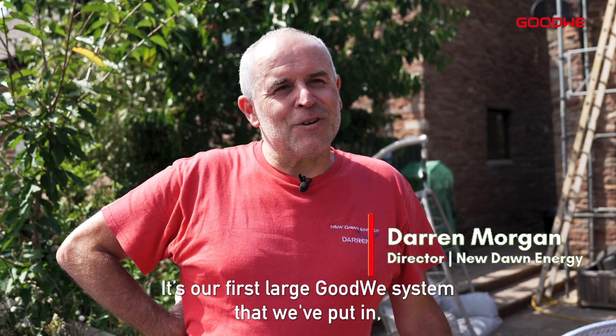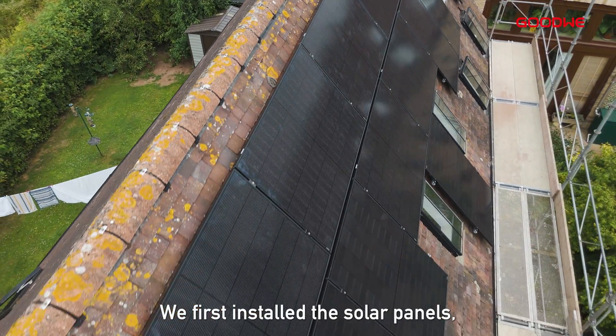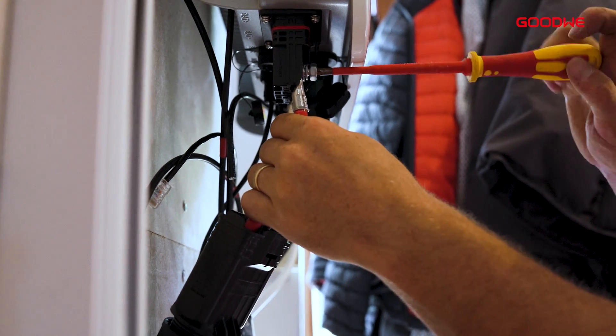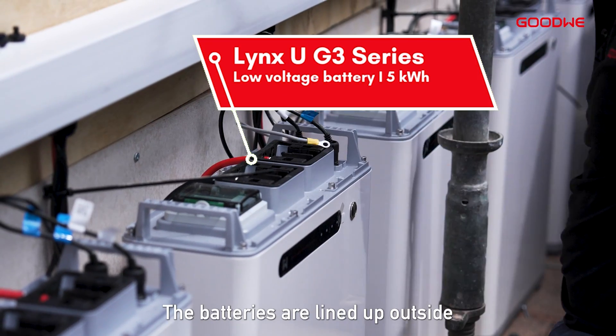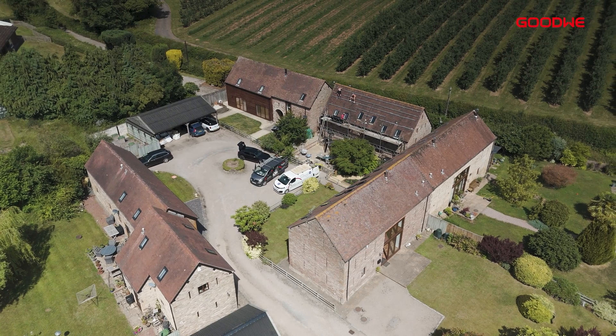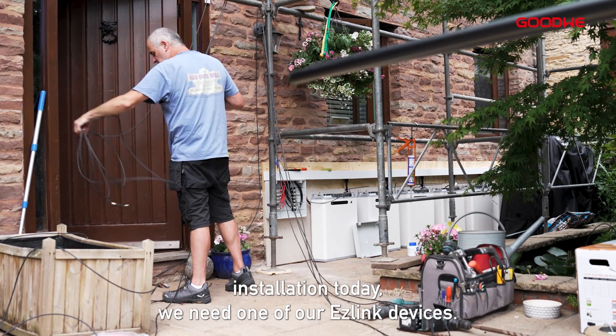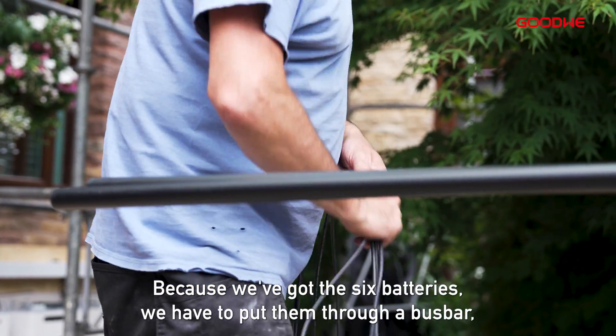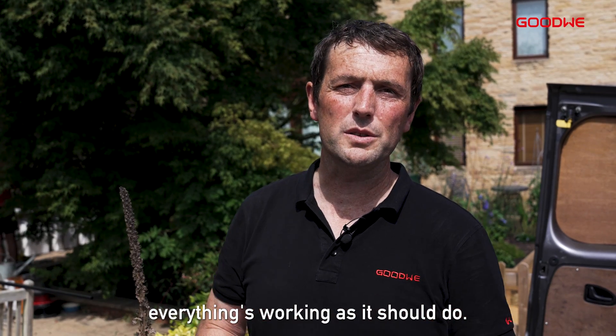It's the first large GoodWe system that we've put in. We first installed solar panels and put the mounting system on. The inverters themselves are installed inside the house and the batteries are lined up outside on fireproof boarding. With the parallel installation today we need one of our EasyLink devices. Because we've got six batteries, we have to put them through a bus bar, and each length of cable is the same for each battery to ensure everything's working as it should.